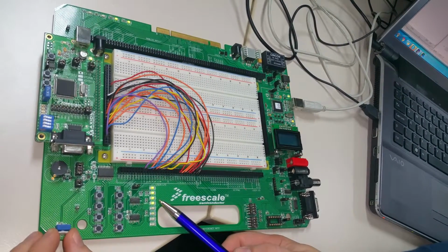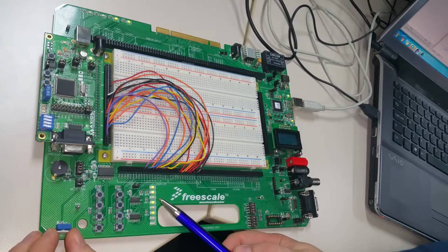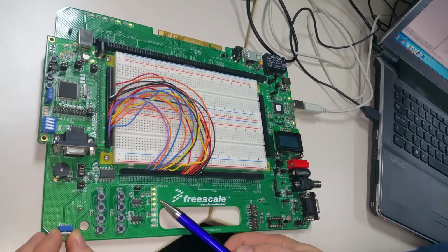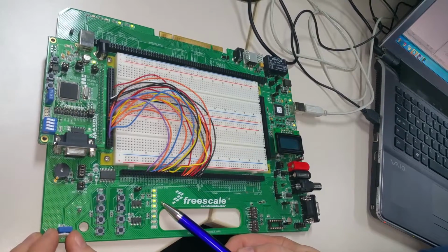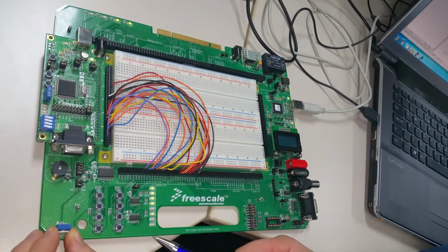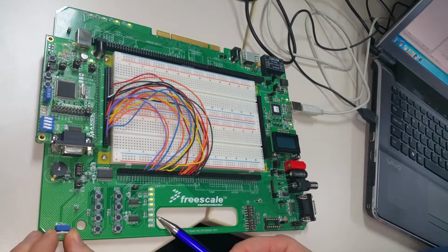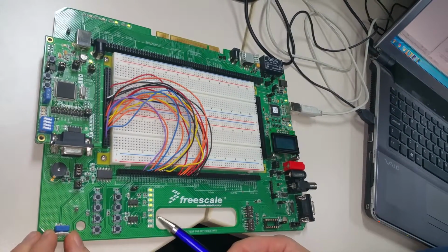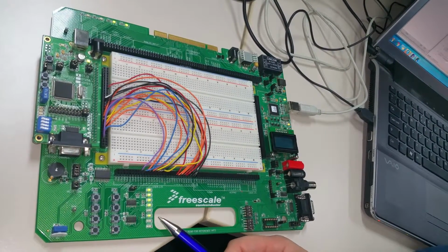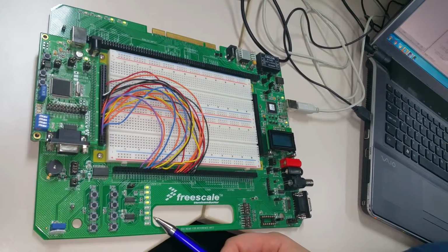You may also see, if I go over the 100 degree mark, the LED number 3 comes on. This indicates that the oven door lock is on, which is a safety function. And as I achieve the set point, you can see that the LED is now on permanently. This means that the oven desired temperature has met the oven actual temperature.